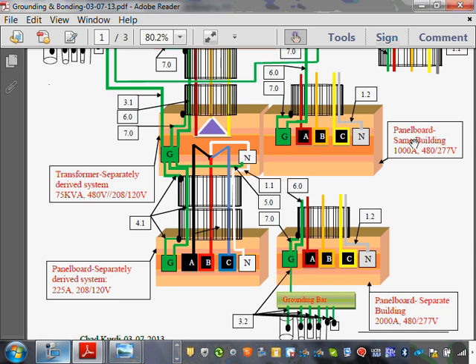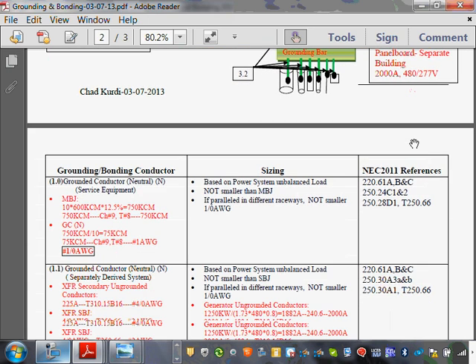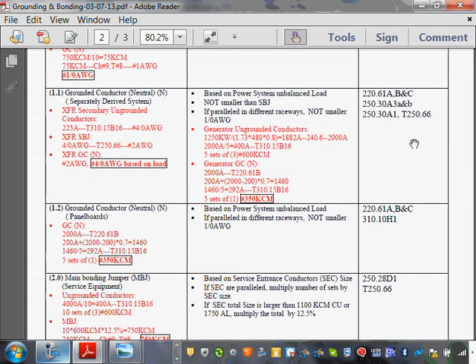Then you have to pull a grounded conductor. So let's go size the grounded conductor, 1.1. That's the neutral coming out of the transformer. A lot of us engineers, I'm sure you agree, if you have anything 300 amps or less, full neutral, especially panels 480, 277, 208, 120. It's not worth derating a neutral on a system 300 amps or less. After 300 amps, you start. Typically 225 amp. Why? Because there's a lot of neutral load in it. These are feeding lights, or in this case, receptacles and lights. A lot of neutral load.